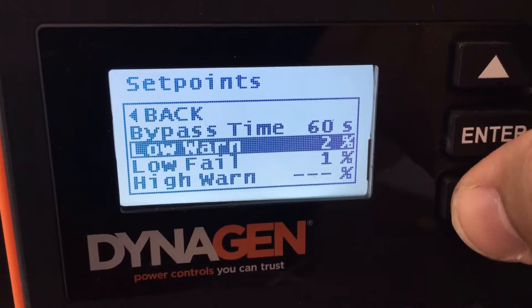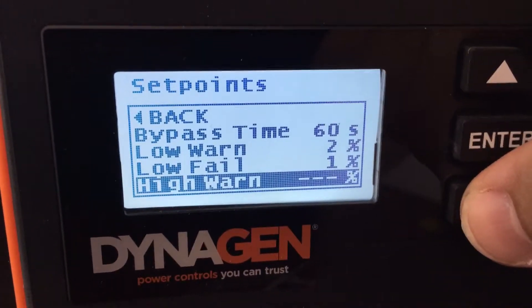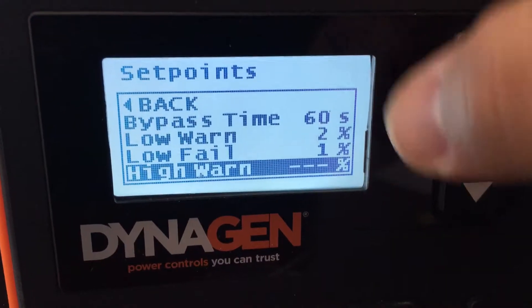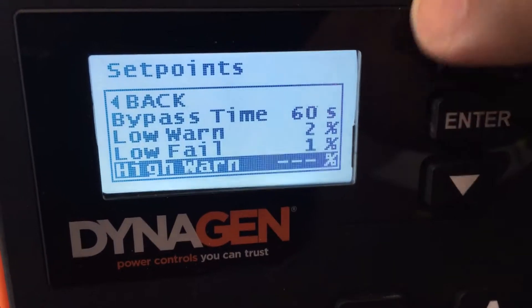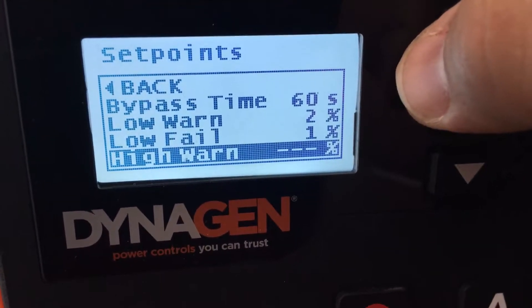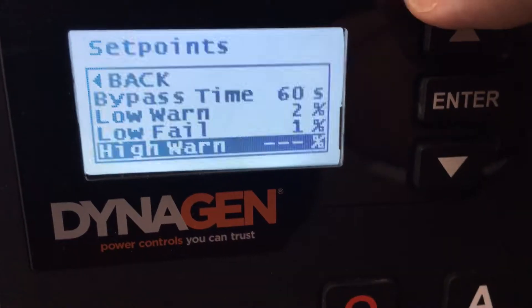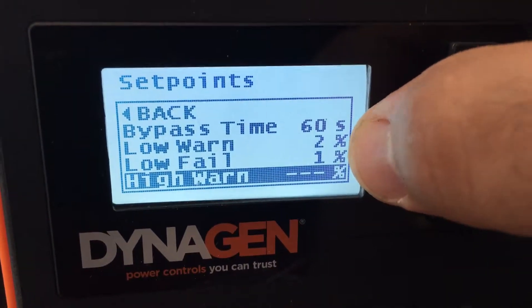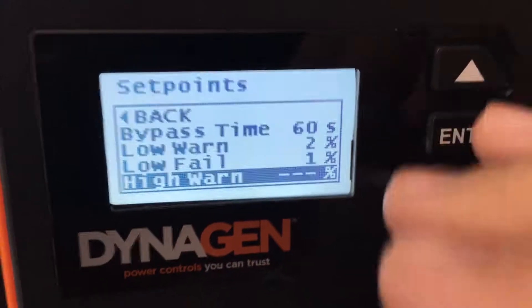What the low warning level is, what the low failure level is, what the high warning level is, and what the high failure level is. You're going to have to experiment here and see what high and low is. It is not a linear scale — it's only about 12 steps because of the shallow tank. We can't get very accurate feedback from the sensor on really how much is in the tank. You may find your warning could be between 2 to 10% for an empty tank, so play with that.